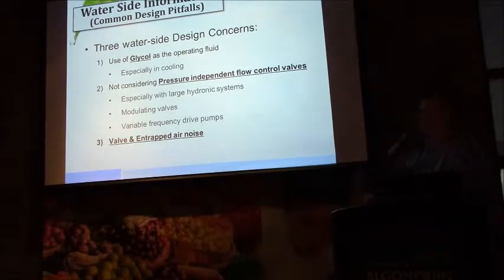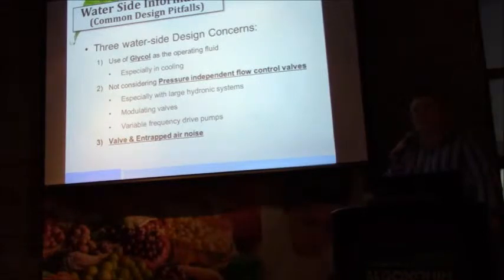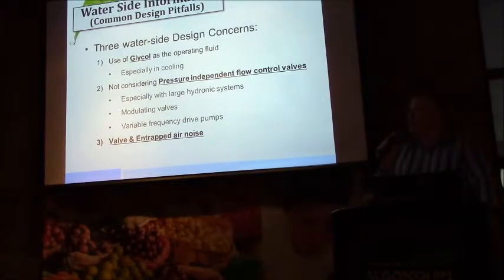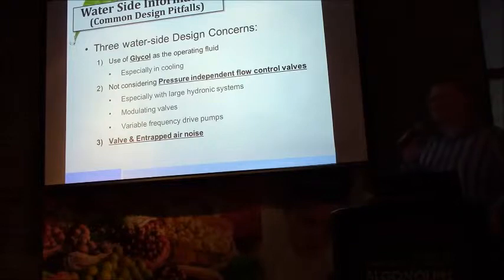Why would we have glycol in the loop? The opportunity for airside free cooling with active beams is limited because we've cut the total air volume into the space conceivably to half of what you would expect in an all-air system. And so the solution then comes to us by way of waterside free cooling. And that could be something creative, like a coil installed on the inlet of an air handling makeup unit, or makeup air handling unit, sorry, to scavenge heat from the building and effectively deliver it to the outside airstream, given that the energy has been paid for, be it through either the occupants or the lighting load or the equipment.